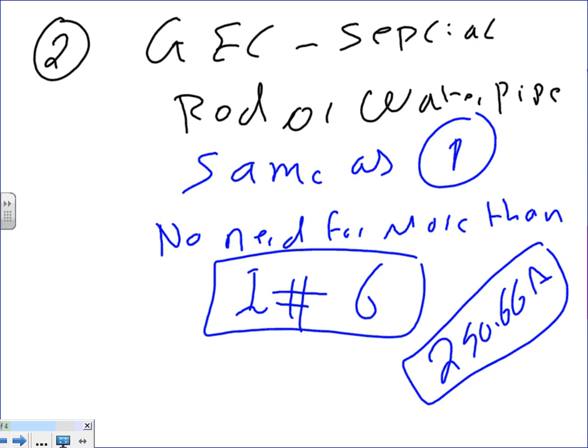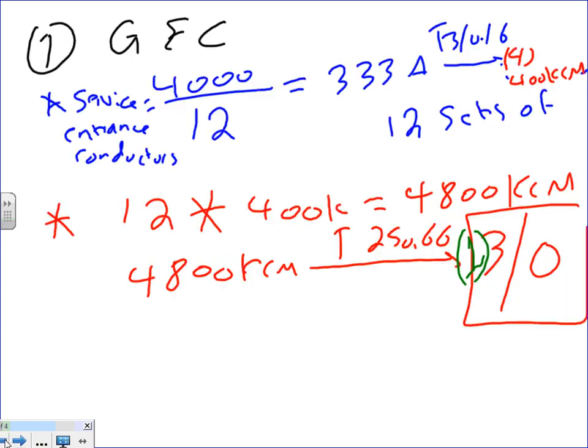Before we move to number 3, main bonding jumper, piece of cake. The difference between what we've done before and this sheet is that it shows where all these have to be located most of the time. Any question about the grounding electrode conductor? 1 and 2 are the same type, but 2 is special because it's going to a rod. And if you go to a plate, I can't remember, it's number 4, there's a couple of special ones. I don't have the plate here.